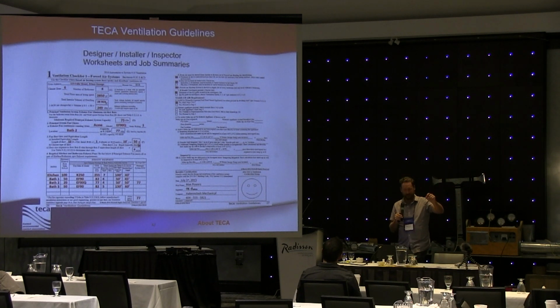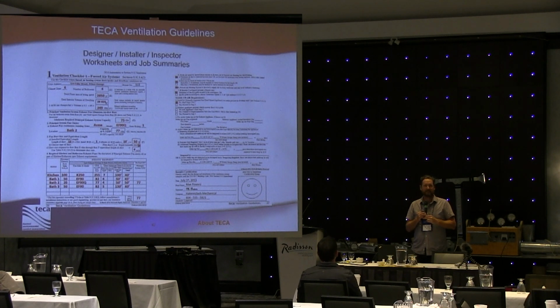I get a lot of calls from people who are just about done their kitchen reno. They say, I'm just about done my kitchen reno, I need a gas contractor to come in and hook up my gas range, and I need somebody to put my hood fan in. And you show up and they've got a 1200 CFM hood fan with a 5-inch duct that goes to the outside. And I know for a fact that is not going to move 1200 CFM, and it's going to be noisy, and it's going to waste energy, and it's not going to work. So we get into that situation quite often.